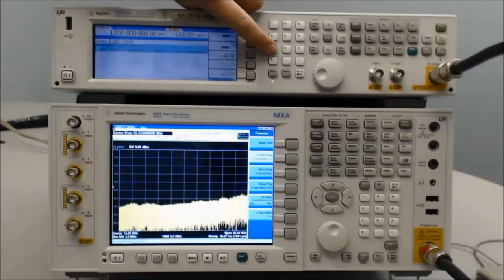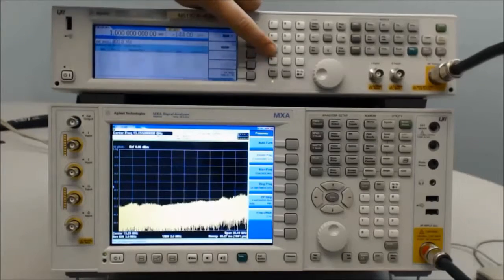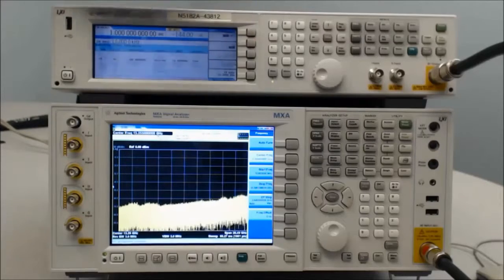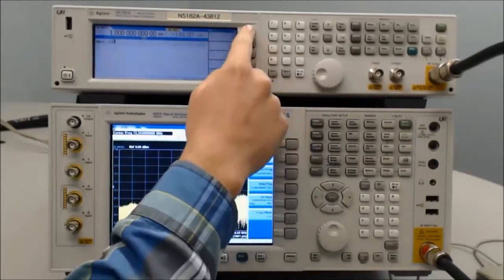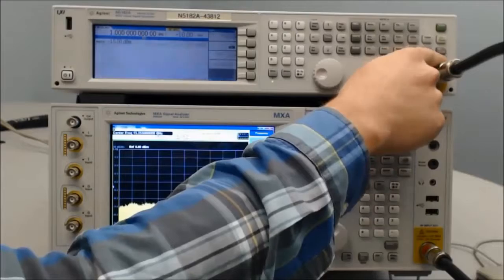From here, we can change the FM deviation to 100 kHz and change the FM rate to 10 kHz. Turn on the FM. We want to change the amplitude to minus 10 dBm. Ensure the modulation is on and the RF output is on.